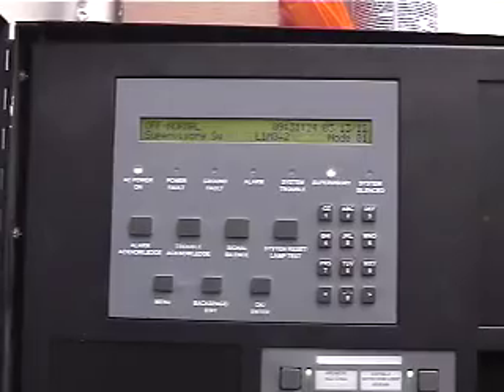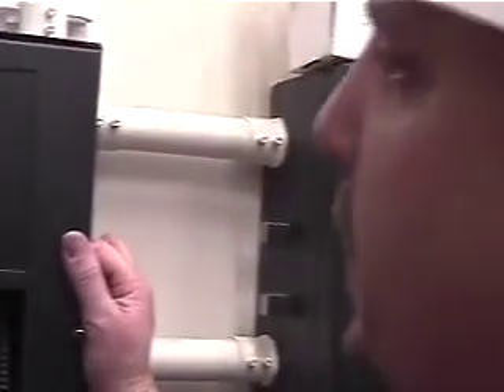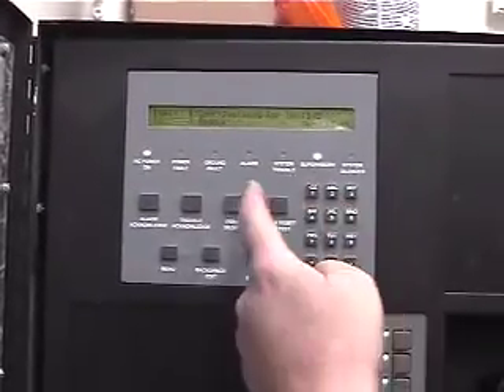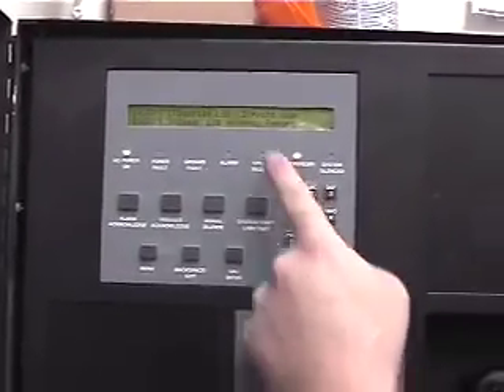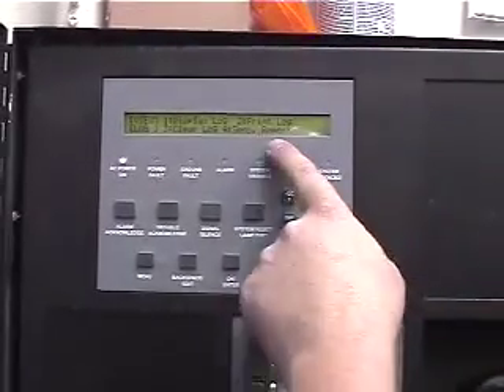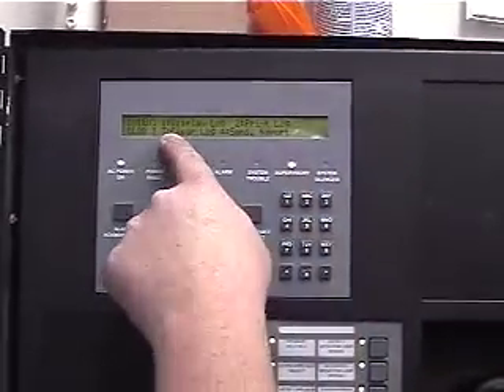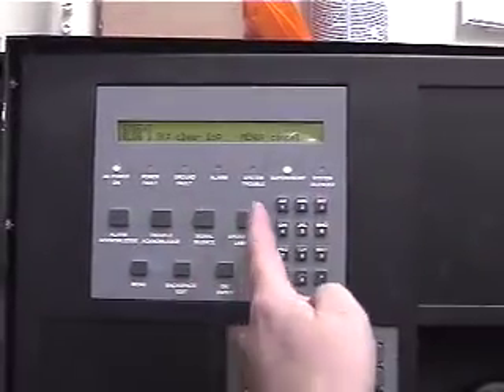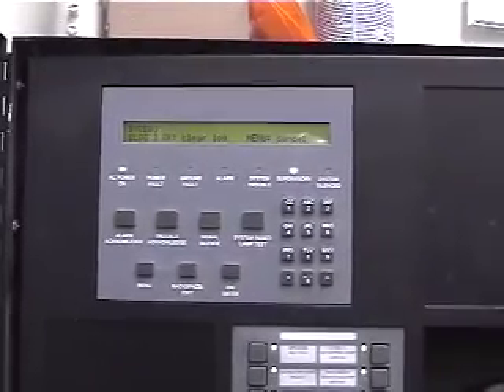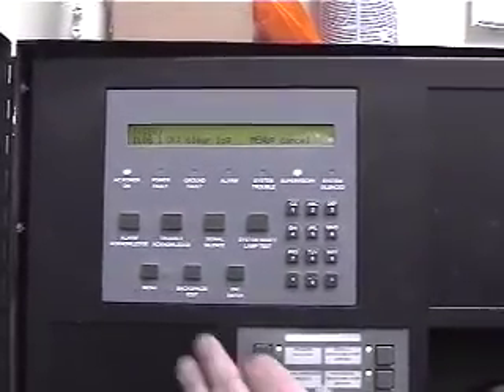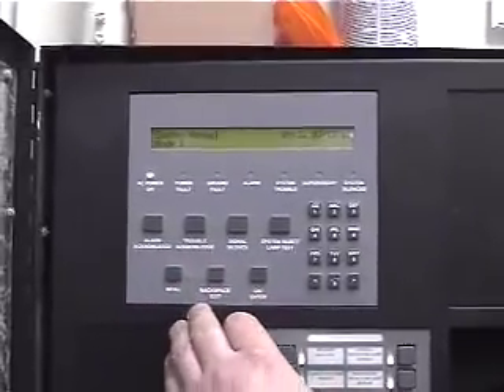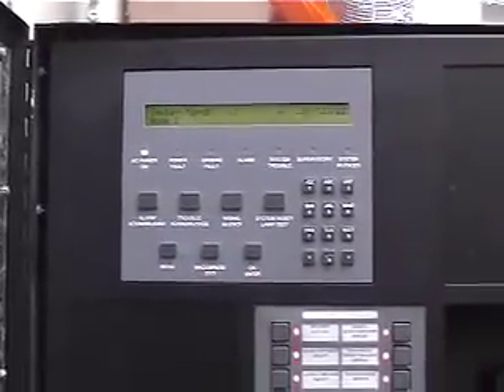The print log, you have to have a printer or a hyperterminal on a computer, and a cable for that. So on your log, you wouldn't be able to do the print unless you have that. You got your sensitivity, you got a clear log, so if you press 3, it'll say okay to clear log, you can okay, and it's cleared the whole log, and you can start over. So if you had too many faults in there and you wanted to start it over, you can clear it out.